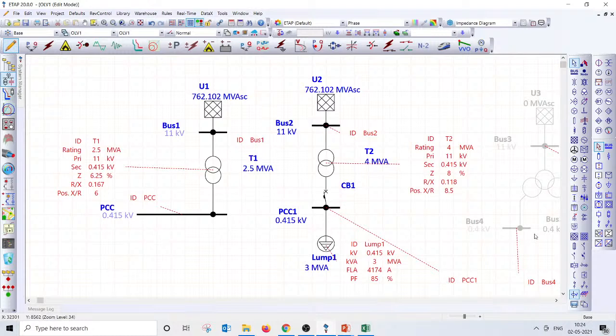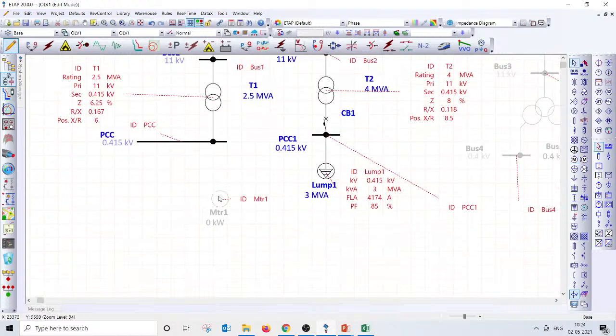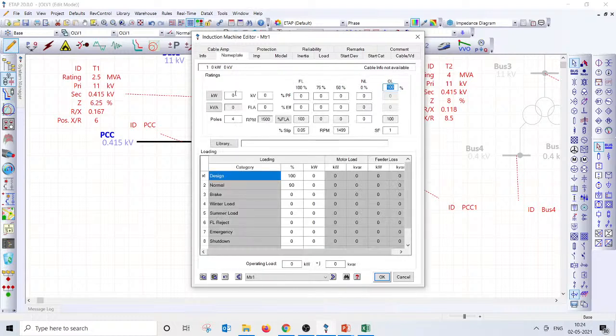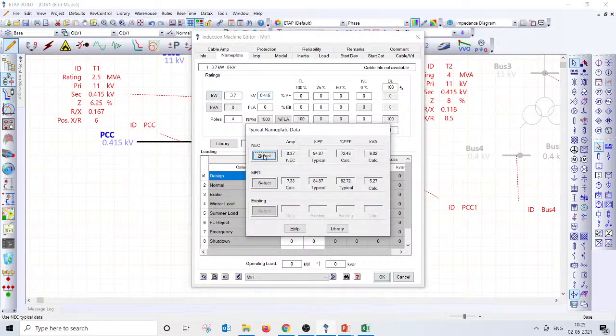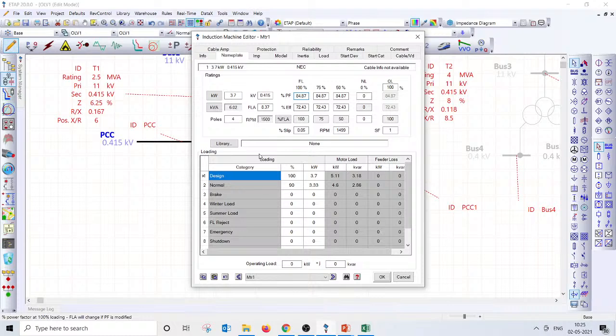and try to add a motor, sorry, of 3.7 kilowatt. Our question today is why this 3.7 kilowatt motor should not be connected at PCC. So the answer is here. A 3.7 kilowatt motor with 415 volt. I have not used any data, it's a typical data; the efficiency is 72%. It is too low. I'm not really sure why it is that low. We will try to find out, maybe something else. Okay, manufacturer data is better, 82%. Yeah, 70% efficiency is too low.